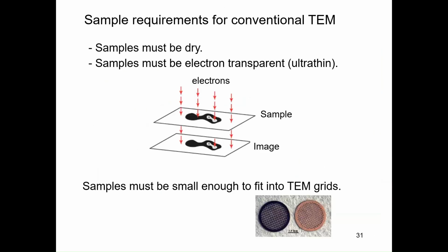So the sample requirements for conventional TEM: again, samples must be dry, and also must be electron transparent, ultra thin, because the electron beam comes from the top and has to transmit through the samples. If the sample has an electron dense area, the electrons get scattered and don't get to the detector, so that area would be black. But if there's an electron transparent region, then some electrons are collected by the detector. That is the principle of image formation in a TEM. Another requirement is that samples must be small enough to fit into TEM grids, which are 3 millimeter in diameter.